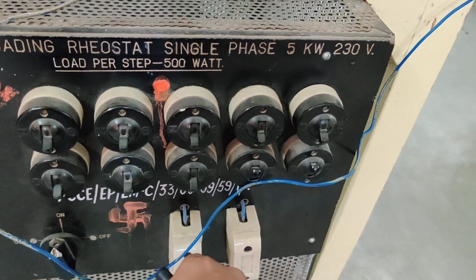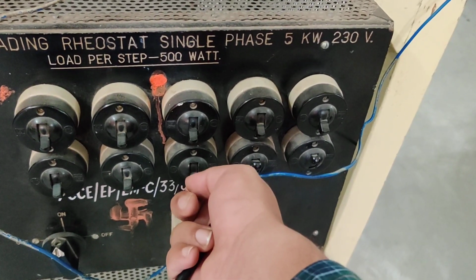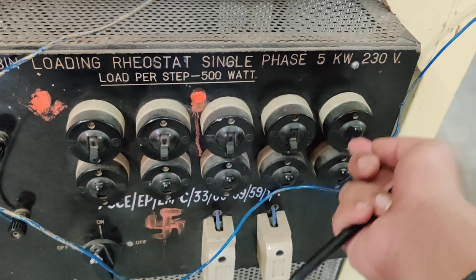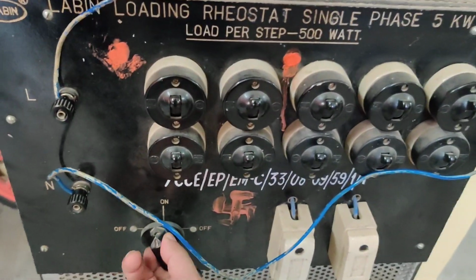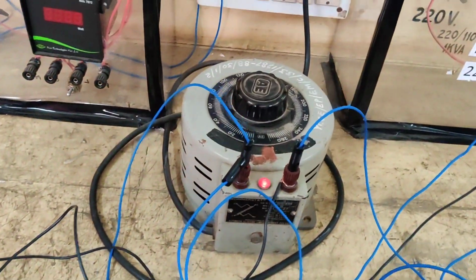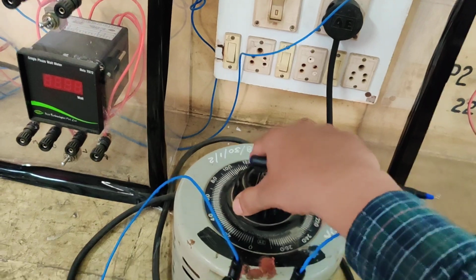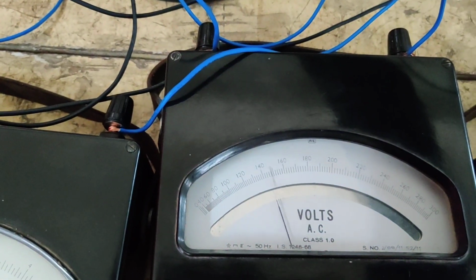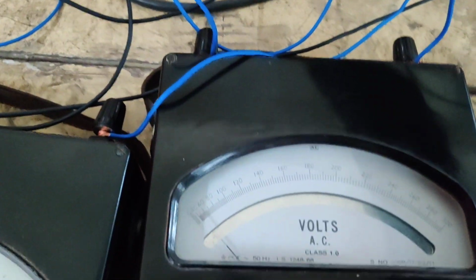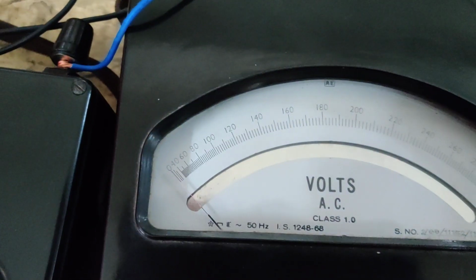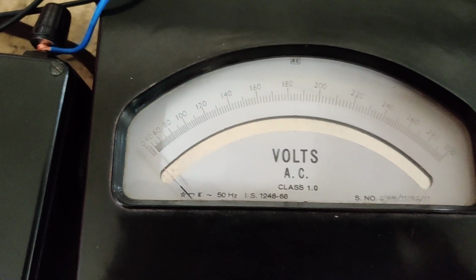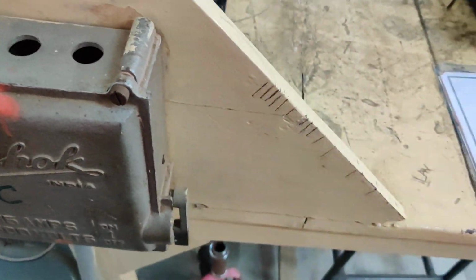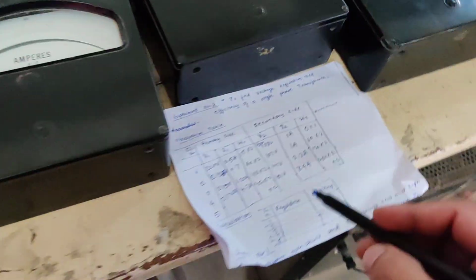Now if you want to off the switches, because we have to off because our readings are over now, this is the pattern with which we are going to off the load and switch off. After that, before directly switch off here, we have to see, we have to reduce the voltage from here by looking here. So now here this particular knob is at 0, and here we are measuring that the voltage on the primary side is also 0. After that we have to switch off this, and before doing anything we have to switch off this one also. Then the next procedure is to go for the calculation.